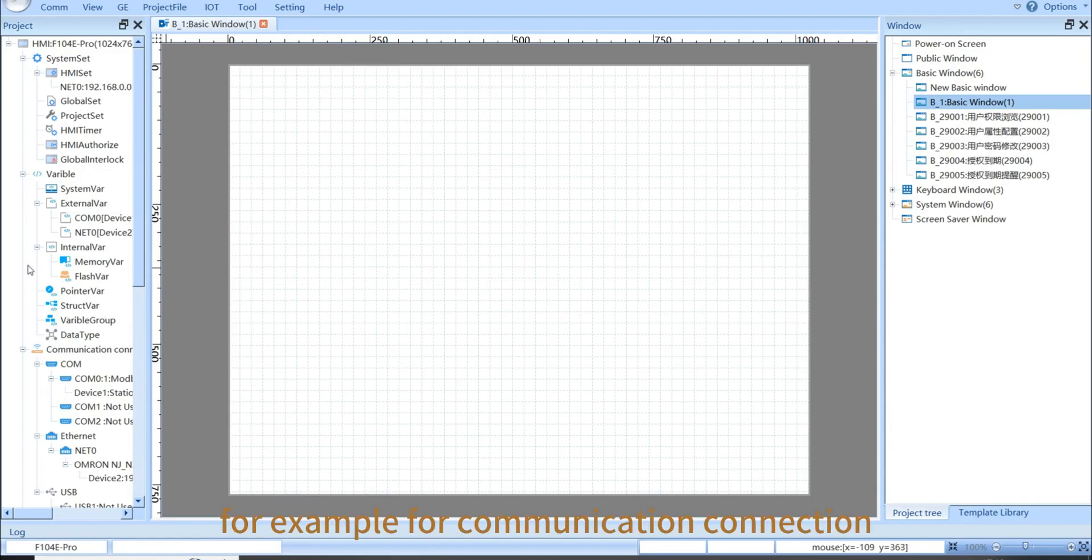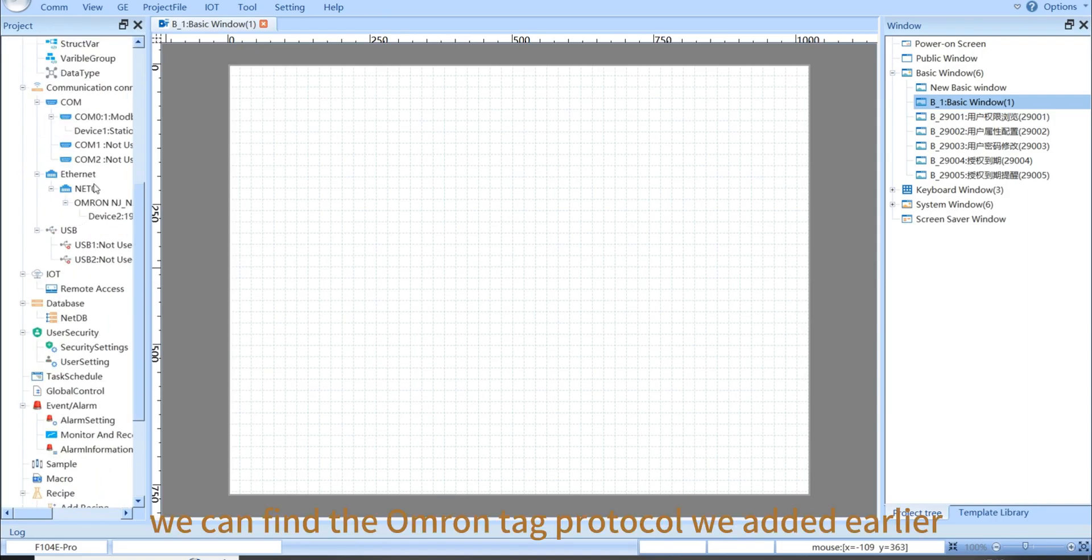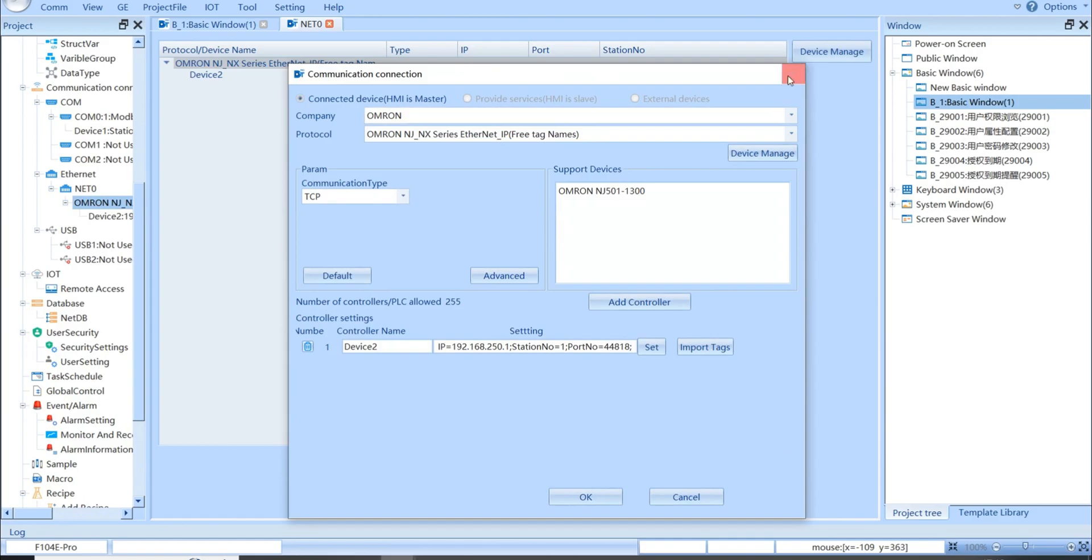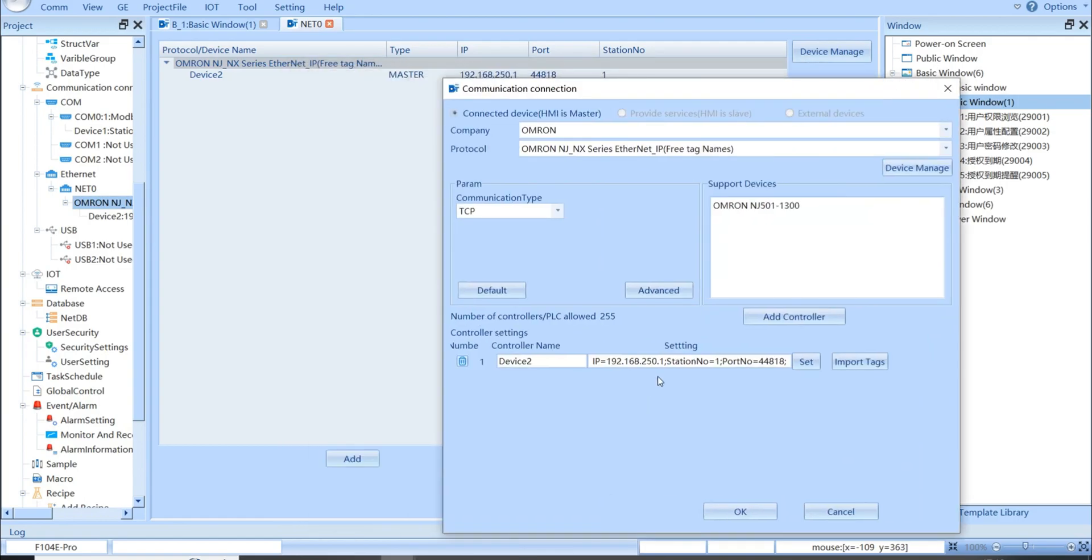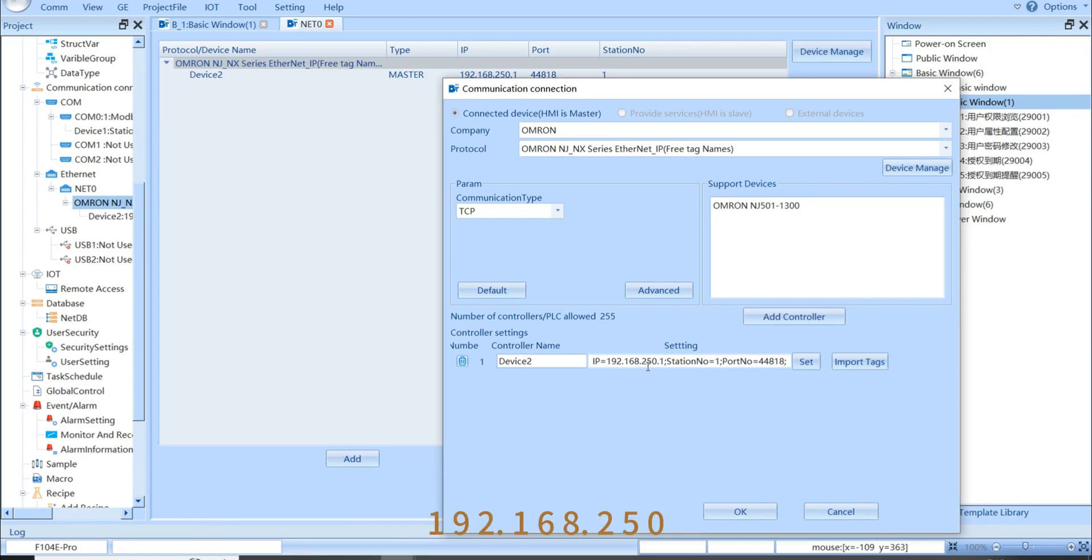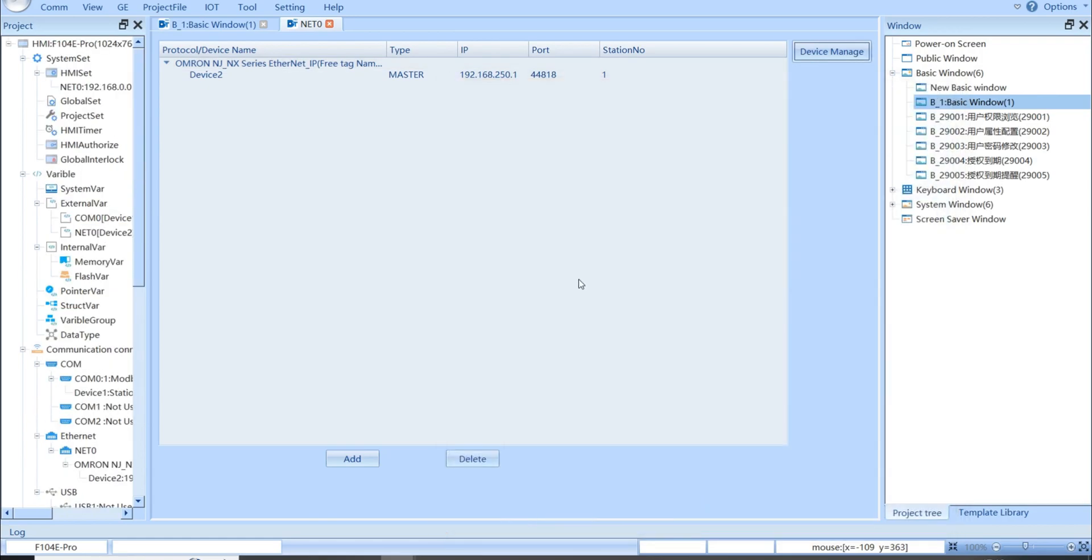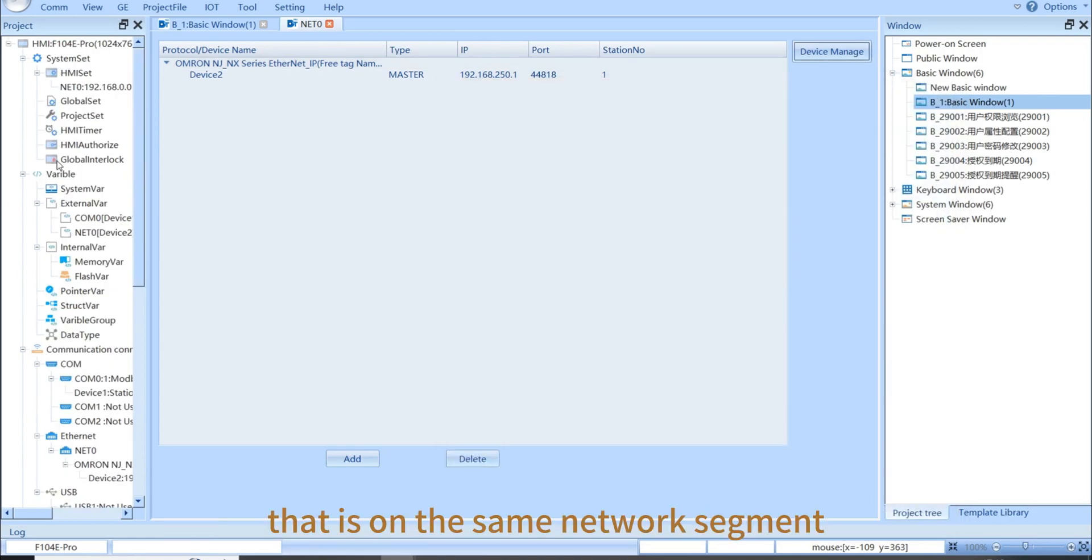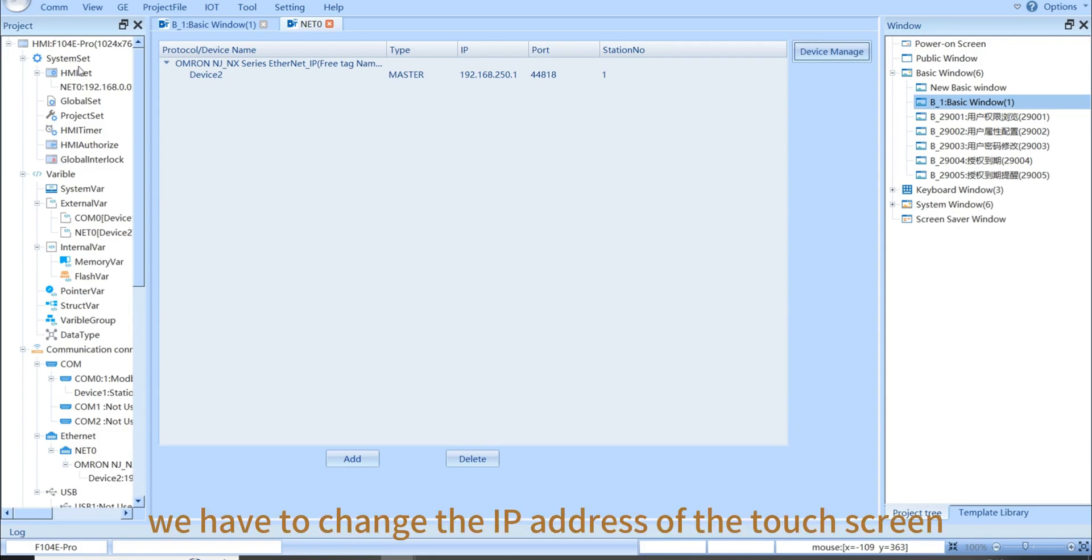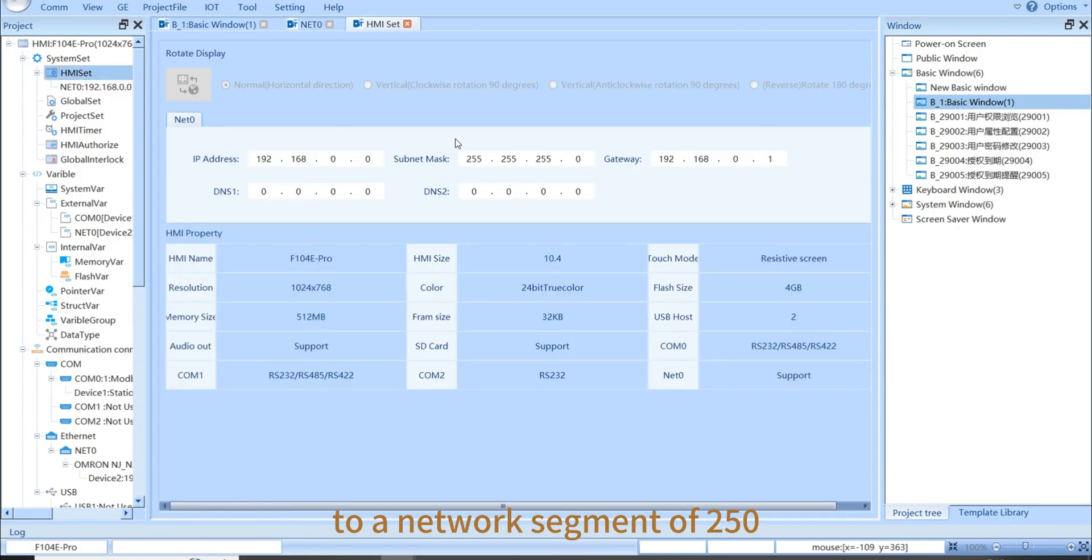For example, for our communication connection, we can find the Omron tag protocol we added earlier. So, we can see the Omron's network segment is 192.168.250 and the touch screen needs to be consistent with it, that is, on the same network segment. So, we have to change the IP address of the touch screen to a network segment of 250.